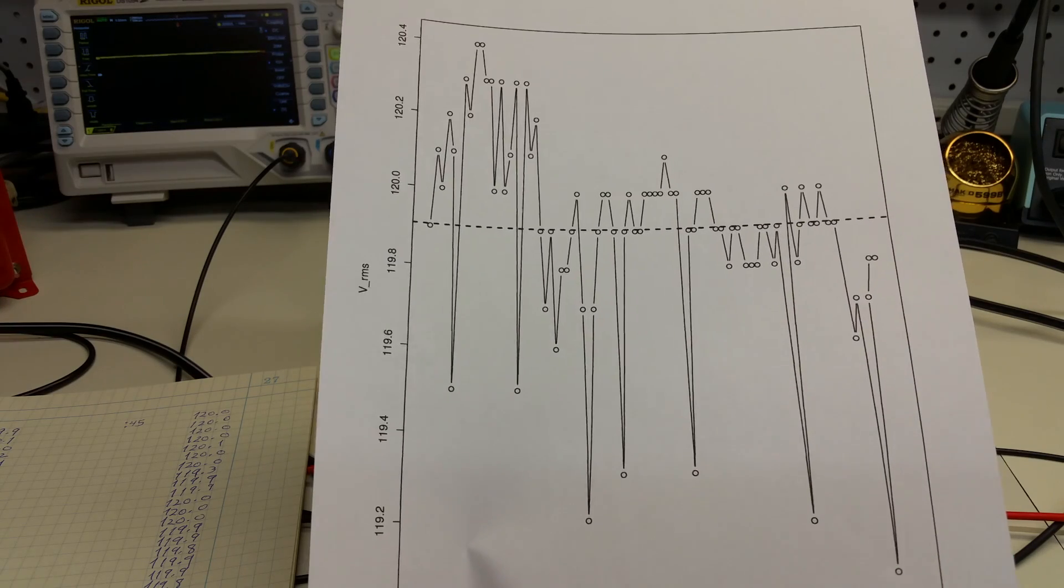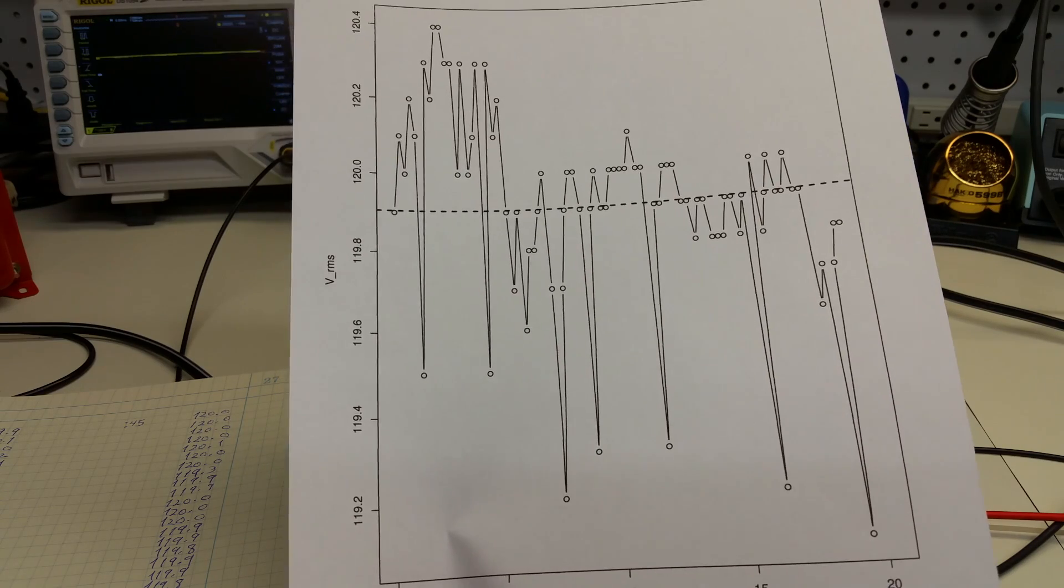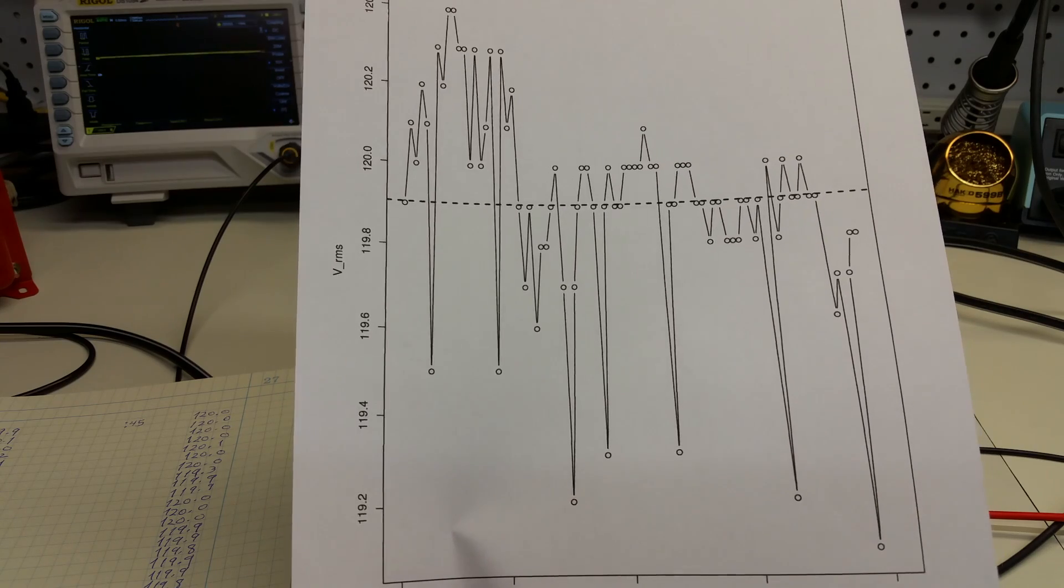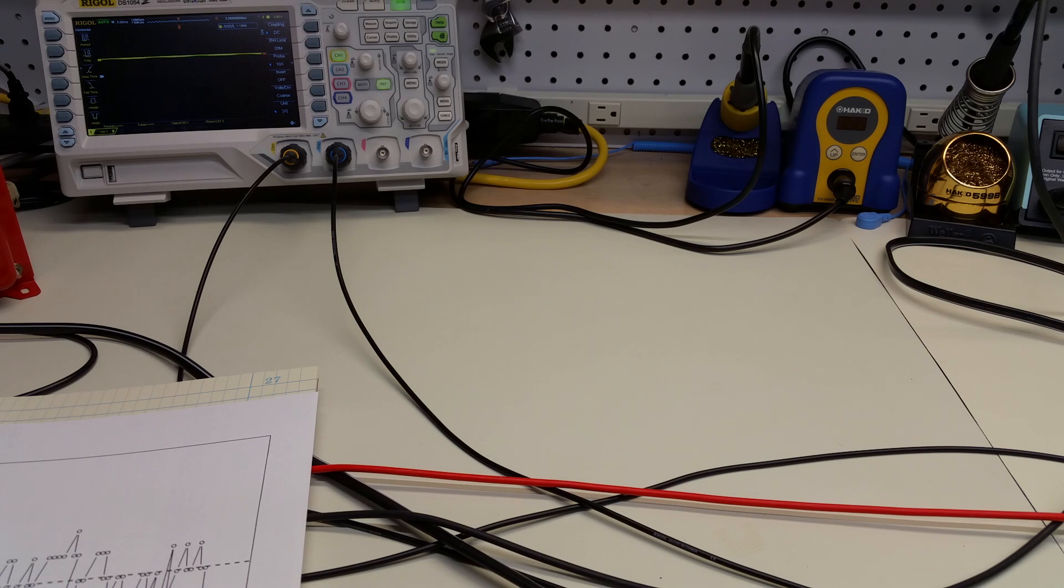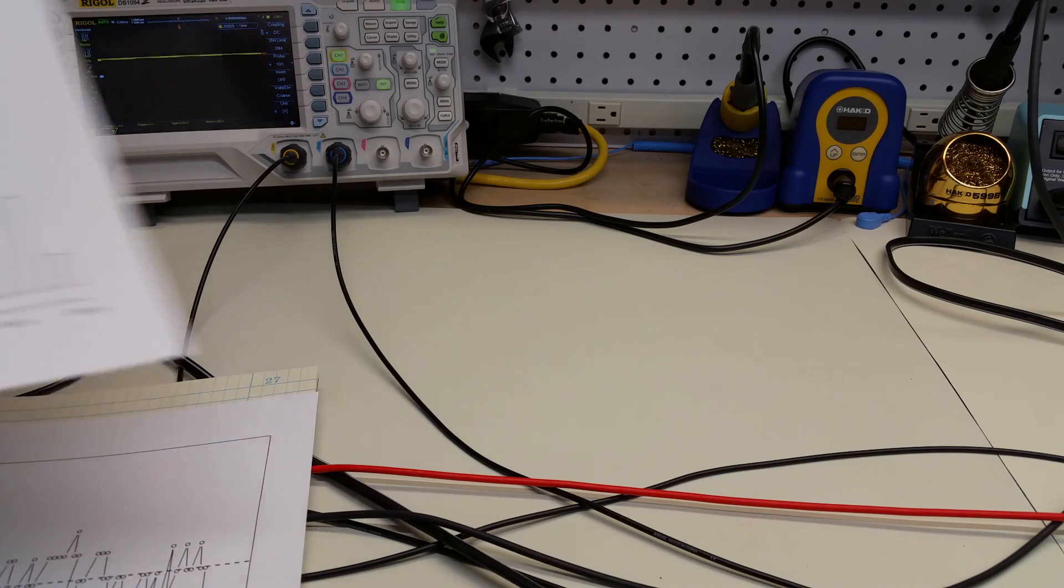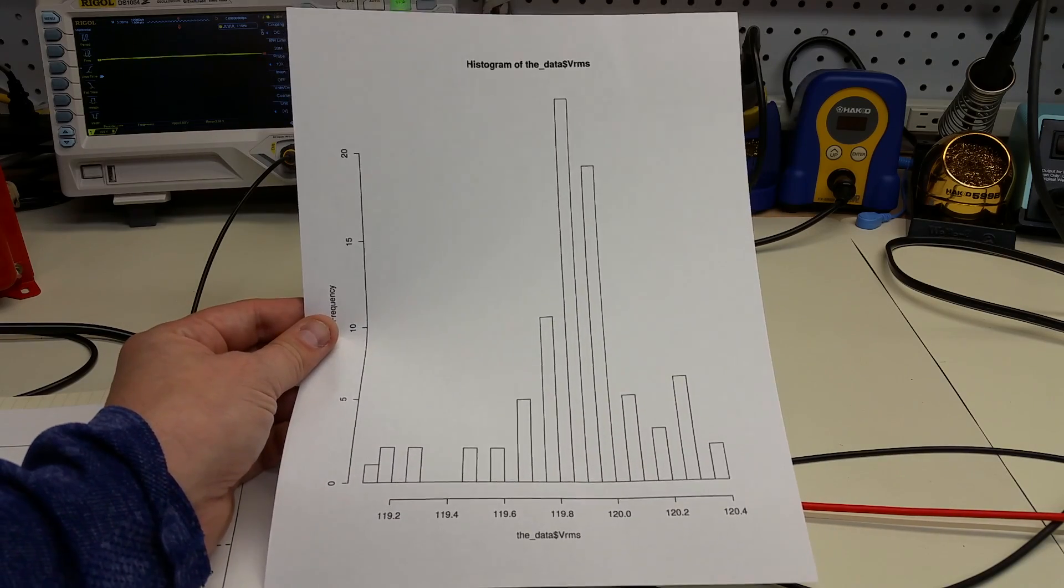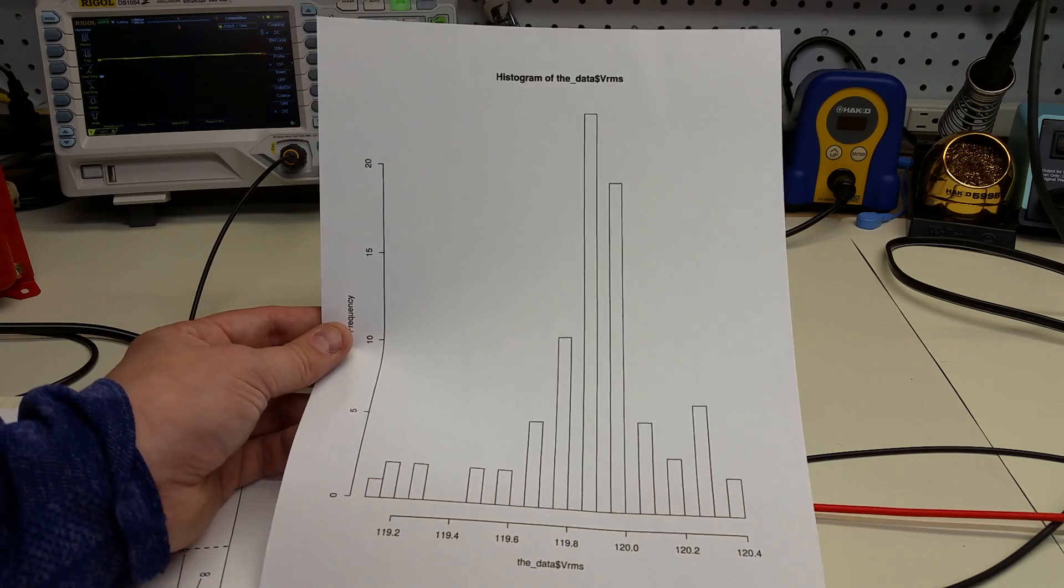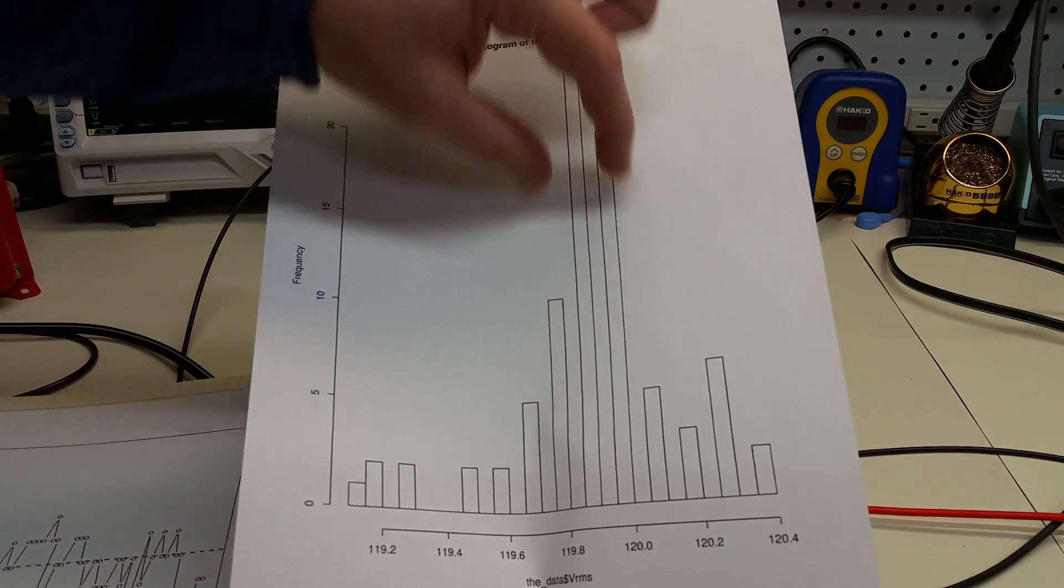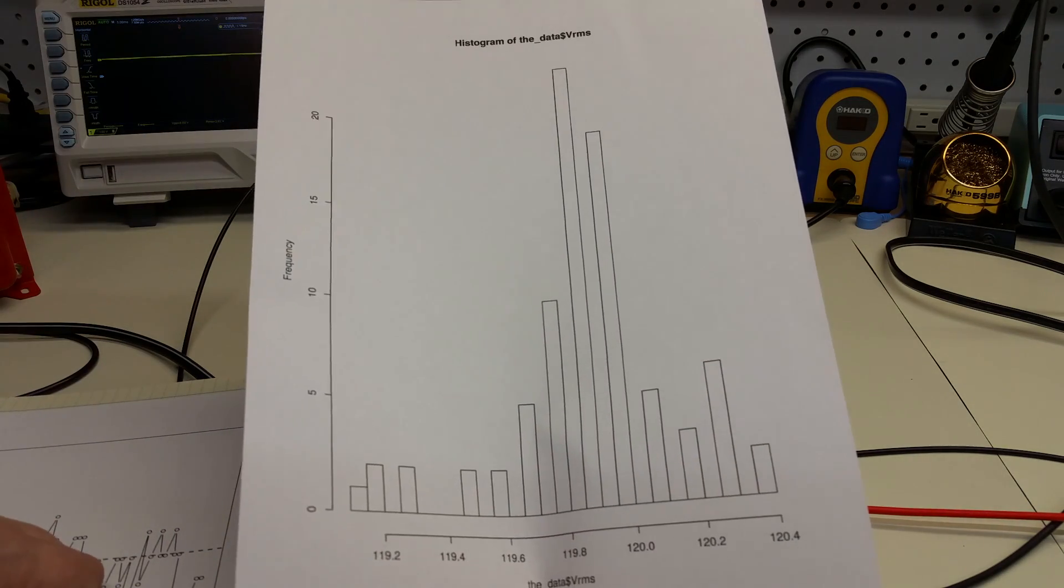So it's a little over a volt difference between the min and the max. Which means that here, in 20 minutes, the line voltage changed by 1 volt, or a little less than 1%. I took these data in the morning. I've done similar things before, not quite as formally as recording the data and plotting them all out. But I've noticed larger deviations over smaller timescales in the evening hours. What do these data look like in terms of frequency of occurrence? Well, this is a histogram of the data. And you see that there's a tail out to the left and out to the right. Most of the data fall within roughly a standard deviation of the mean. So that's reassuring.